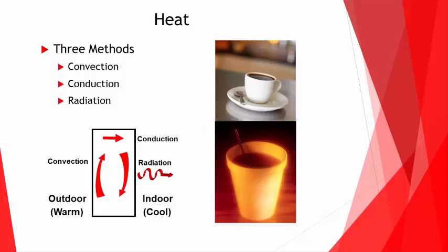So we talk about R value in the building industry, and what is R value? Resistance to heat. Resistance to heat flow, that's right. R value is resistance to heat flow. But what we don't often tell people is R value only measures one form of thermal transmission. Which one is it? Do we know? It only measures conduction, heat transfer by touch. So R value is the only metric that we really have in the building industry, but it does not tell us the entire story because it only measures one form of thermal transmission. It only measures conduction, heat transfer by touch.